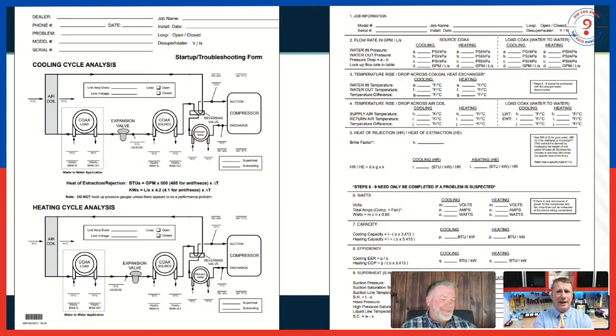So fluid factor is really the restriction or the resistance. Correct. It's based on the type of fluid, right. It's an assigned number that we put to see how much heat that fluid will carry. Yeah. So air is 1.08, kind of depending on your altitude if you want to get really technical, but 1.08 will get it most places. And with water, we use 500 for pure water. And then, depending on what you've got, 490 or 485. It doesn't make that much of a difference in your overall numbers for a methanol or propylene glycol type system.